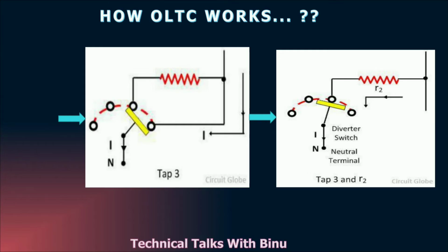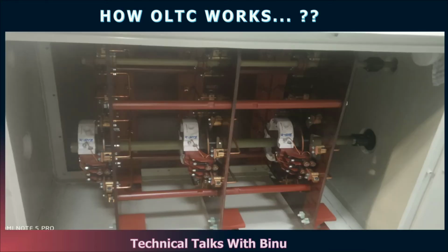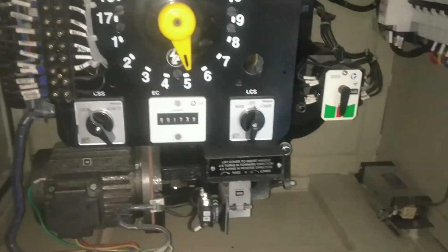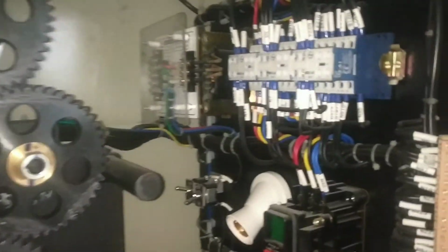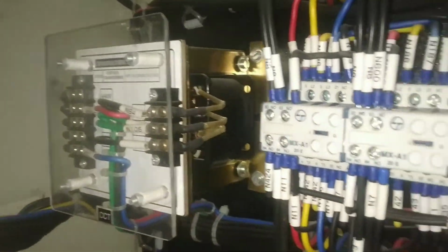And also you can see a resistor in series with the tap and this is to minimize the effects produced by the current during the switching of the tap. What you are seeing now is an actual OLTC and now let's have a deep look into the components of an OLTC. This is the selector switch of an OLTC and you can manually select the tap by rotating the knob. There is a gear mechanism which is present within the OLTC. This helps in switching between the taps.